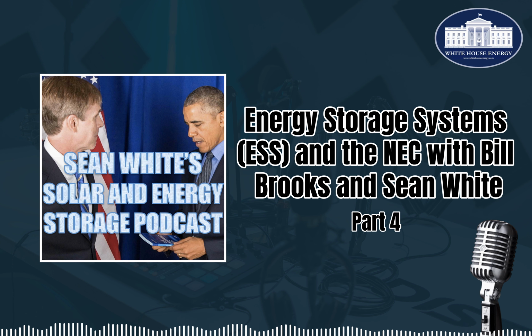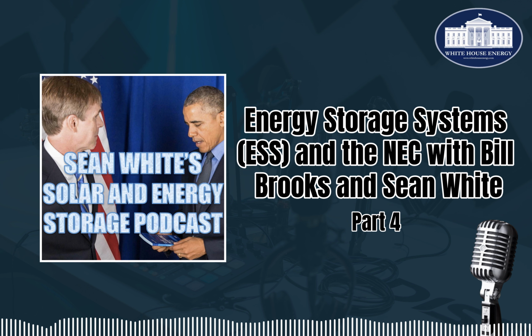So let's say you had one Enphase inverter on a 20 amp breaker. You don't have to use 20 amps there. You would use closer to 1 amp in your calculation.